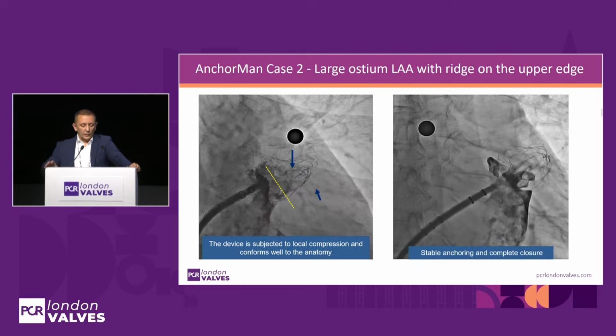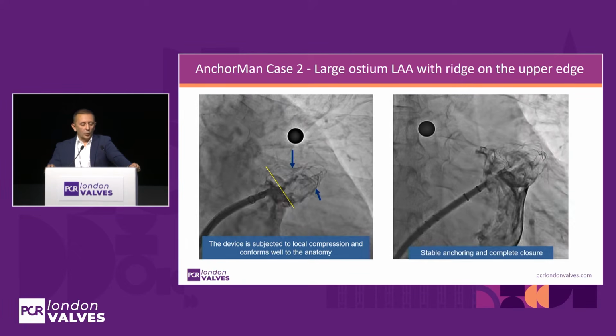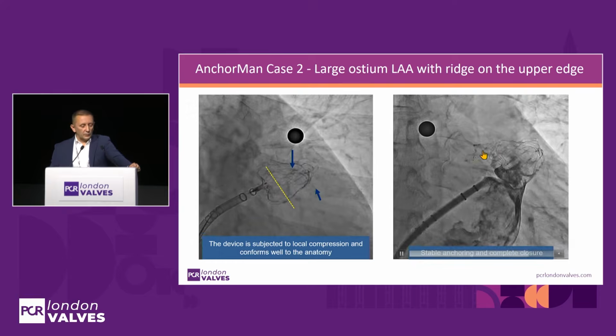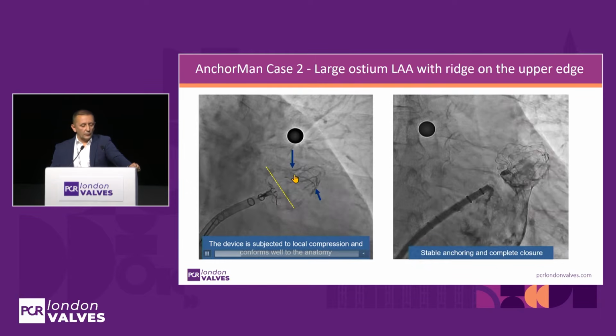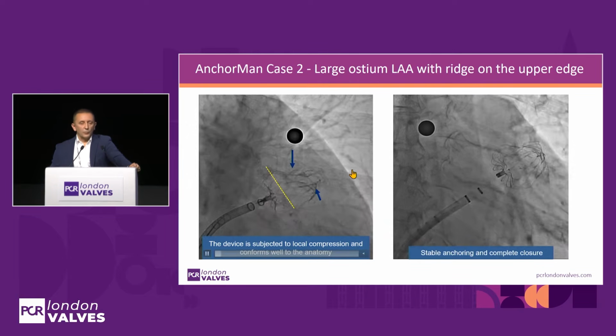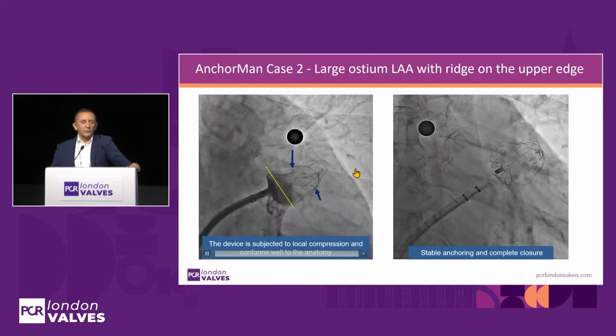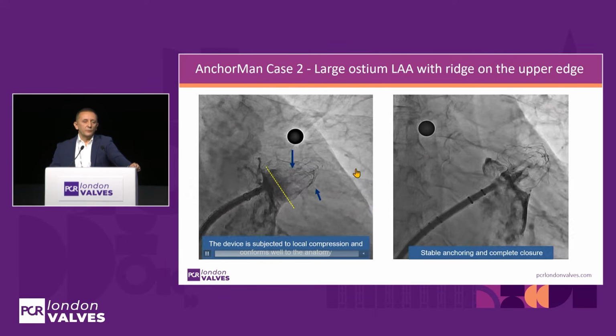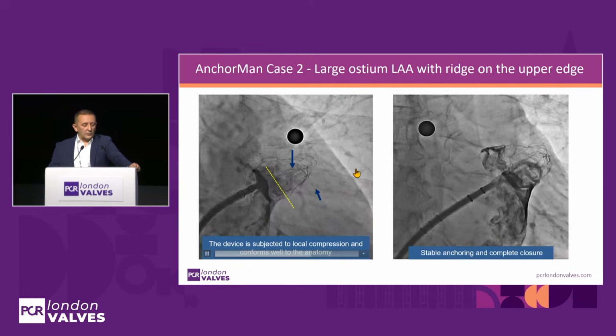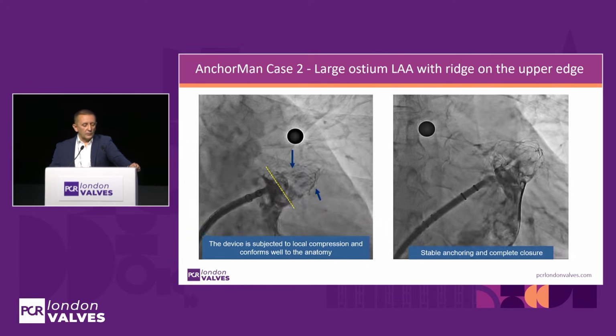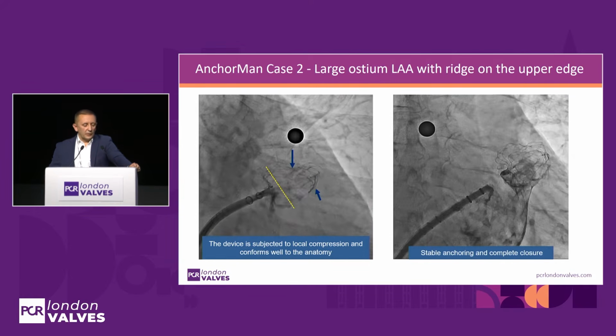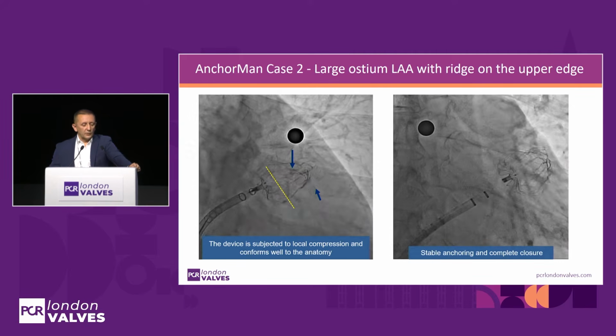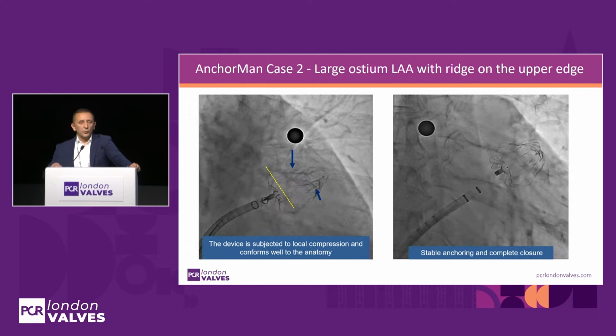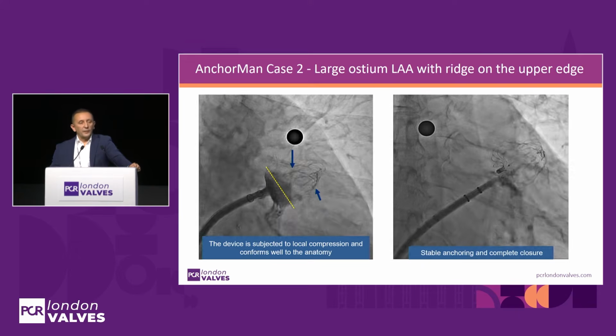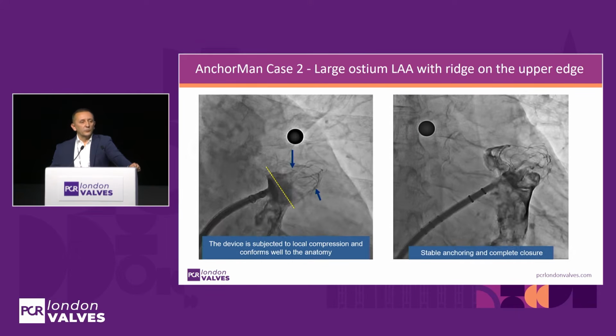We achieved stable anchoring and complete closure. So here in this place, on the left, you see below the blue arrow, the compression. So its advantage of this device, that this device is open cell device. It is very stable, it is conformable, and even if you see that the compression does not transmit into proximal part of the device, and the device remains stable at the ostium.